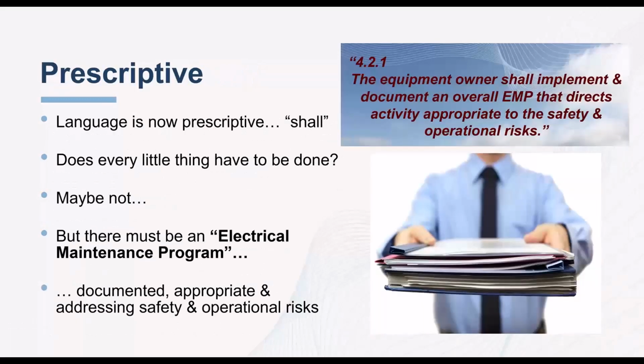One of the things the standard says fairly early on, in chapter 4, is that the equipment owner shall implement and document an overall electrical maintenance plan, abbreviated here as EMP, that directs activity appropriate to the safety and operational risk, with a very key emphasis on safety. There must be a documented plan that tells you how you plan to maintain your equipment, and that you can then document that you are maintaining per that plan. It doesn't tell you what the plan needs to contain, but that you must have one. And it must be appropriate to address safety risks.